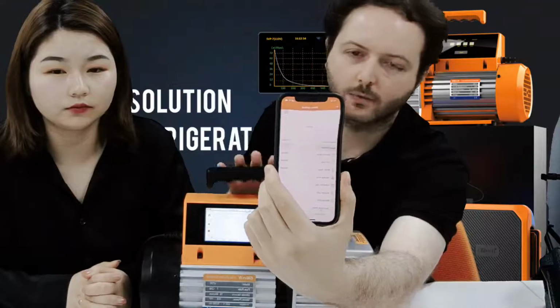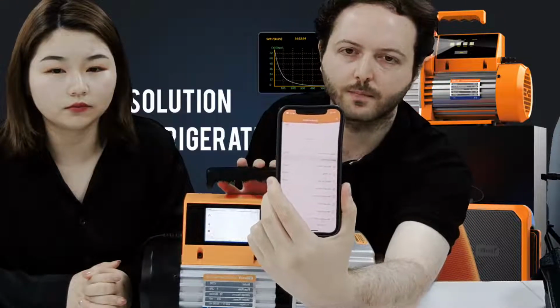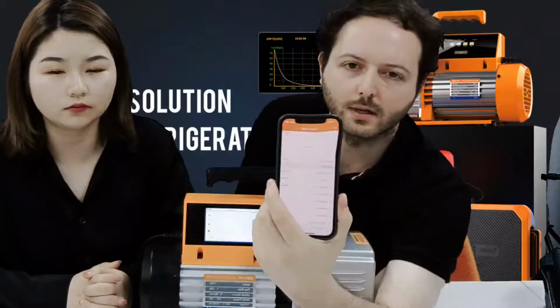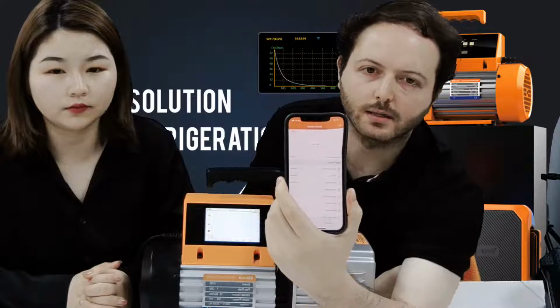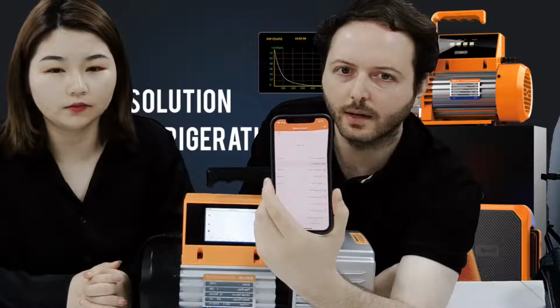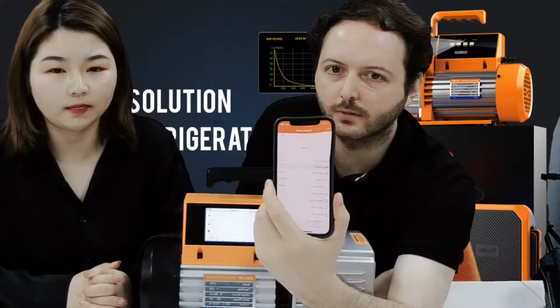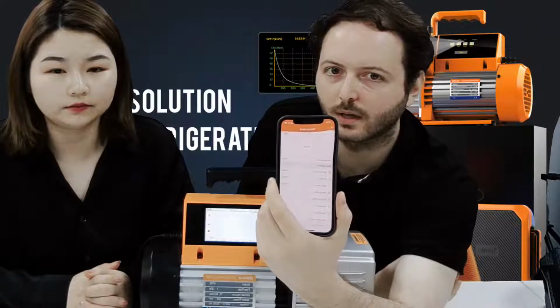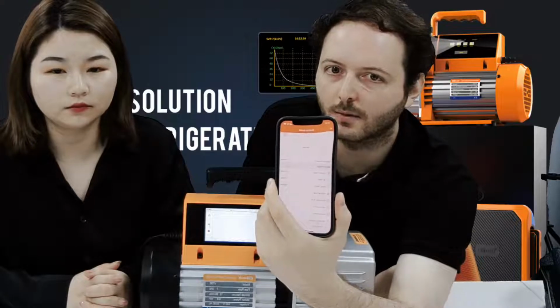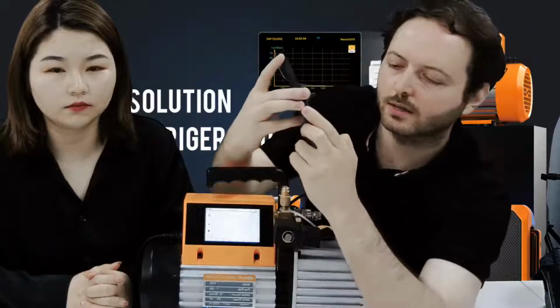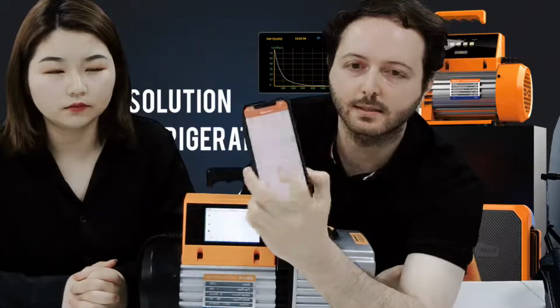In that part, we have this in the Elitech Tools app. We can use the vacuum pump in this app option. In the display part, we can see the vacuum value, oil temperature, motor temperature, and also the estimated finishing time. We can also adjust the logging interval, from 1 second, 3, 10, 30 seconds, up to 5 minutes. For these records, if you want to get the read data option, first we need to turn off the recording, and we can get them in Excel or PDF.